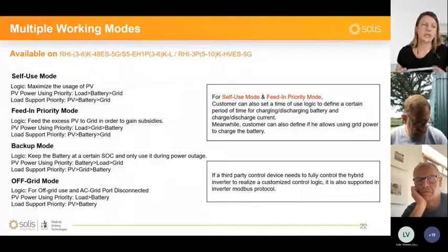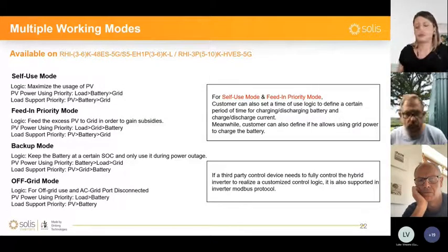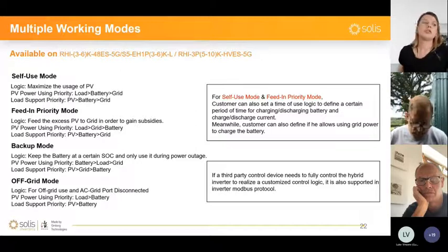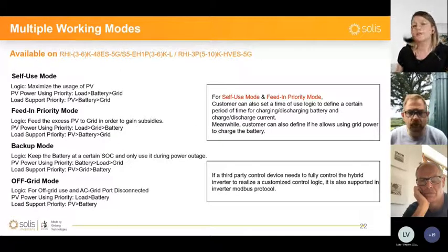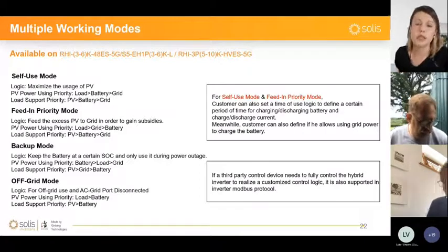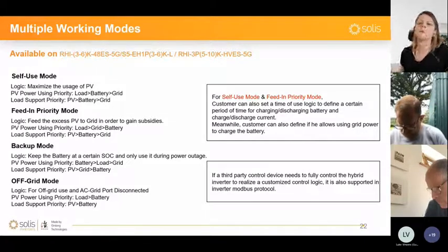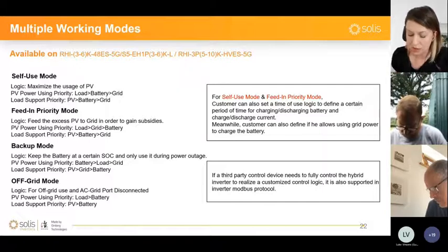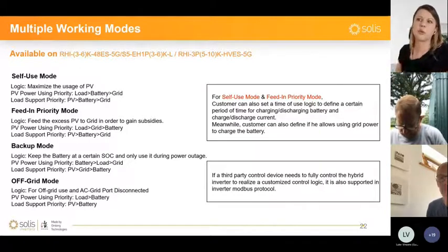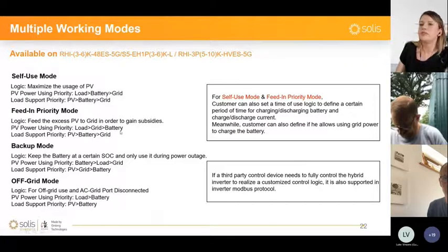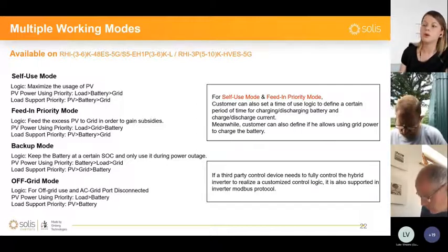Charging from grid helps, for example, during winter times, long periods with low PV irradiation. You're going to need to keep those batteries alive, and this will have to be done not from the PV, but from the grid side. And you also have to explain this to the customer, because those batteries can go on for so long during low PV radiation periods, and they're going to need this. So self-use mode is the default mode in which the system comes.